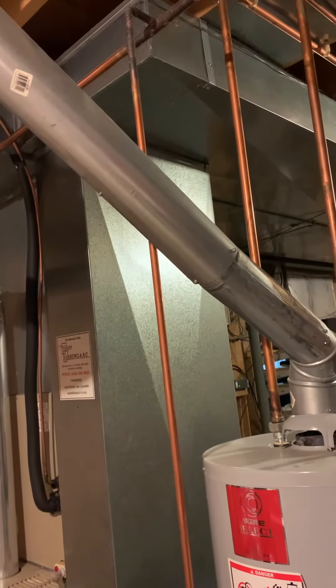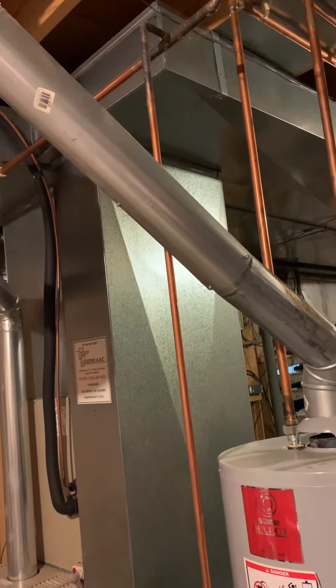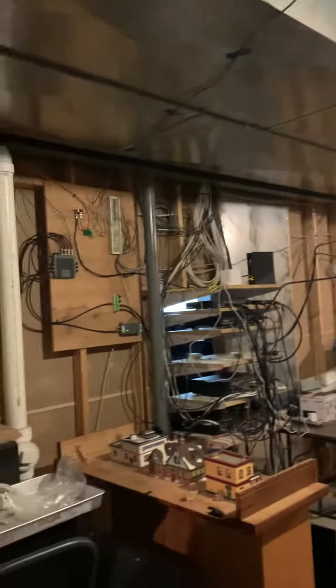One of the things the homeowner is concerned about is there's not enough airflow going into the kitchen area — that tends to stay a little bit warmer. So we want to look at flaring this ductwork out a little bit and get that air going that way, get a little more air there. This is all the bedroom area and it stays pretty comfortable — that's the east side.